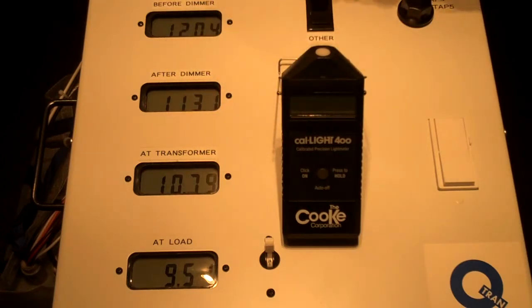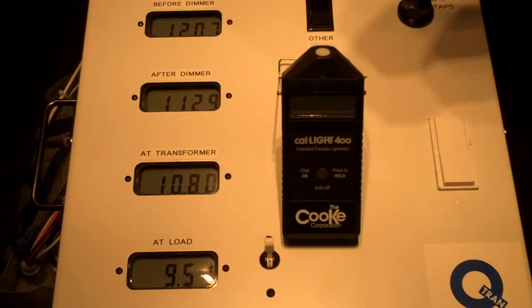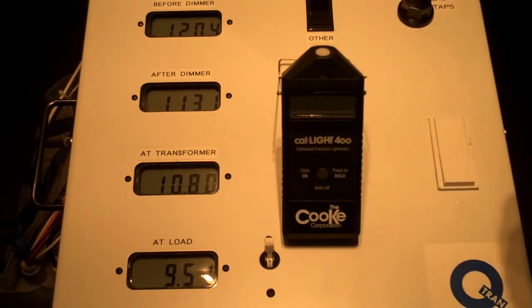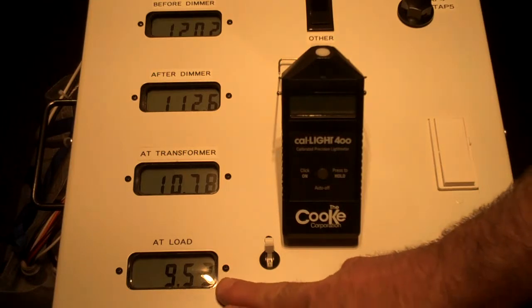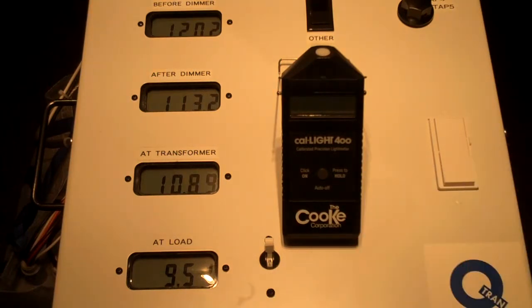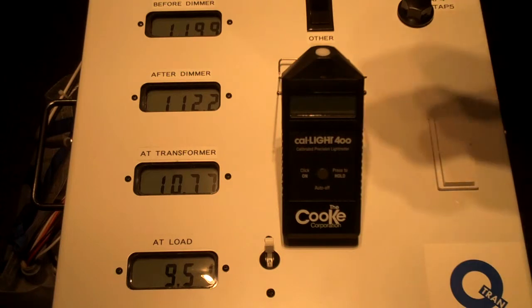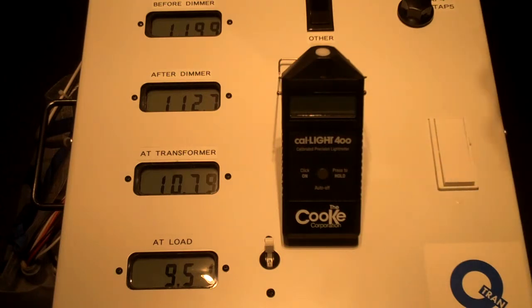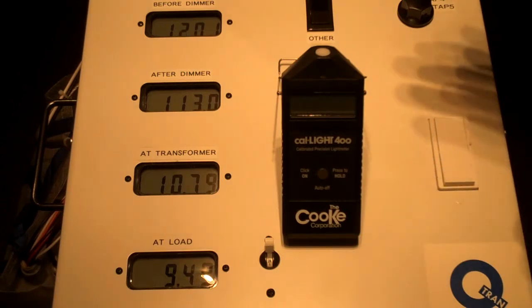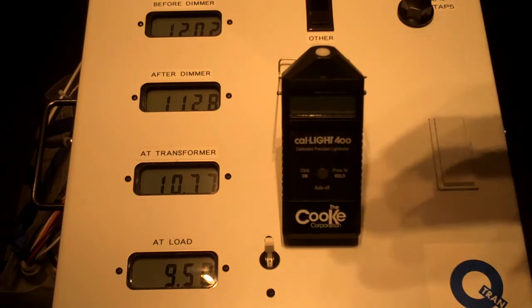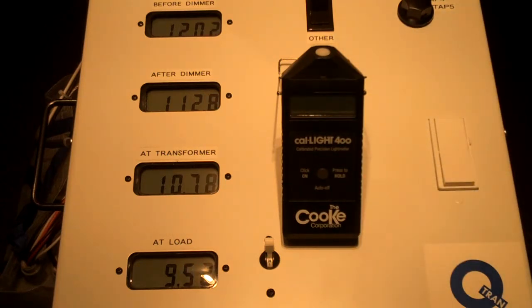We go through 25 feet of 10 gauge wire to a 300 watt load. We happen to have 6 50 watt MR16s on this load, but a 300 watt load is the top end of a load that you can run off of a low voltage transformer. It's 25 amps at 12 volts. So out at our load where we really need that 12 volts, we're down to about 9.5 volts, you'll see here on the bottom meter. What that means is we're getting less than 50% of the light output that we should be getting out of these lamps and still burning the full power to get that. We're just losing that voltage as it travels down that wire to the load.